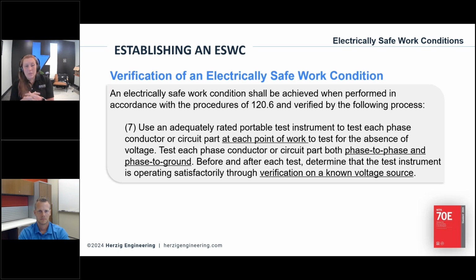To do that, you're going to be testing each phase conductor or circuit part, both phase to phase and phase to ground. I've seen plenty of times, when I'm on site doing an audit or a walkthrough, somebody puts a lead on ground and then probes everything and then walks away. They're like, okay, it's safe. And they didn't check phase to phase. It's a very, very common mistake. Go ahead and do that as well.